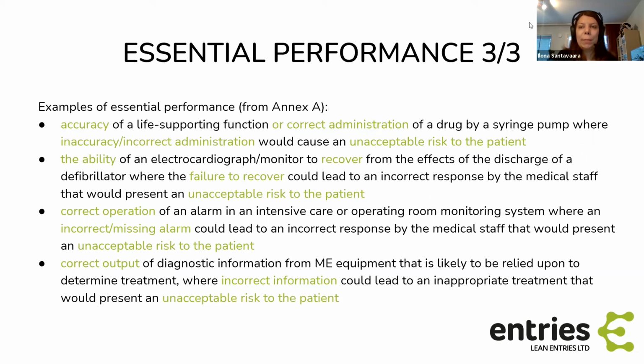And these are from the Annex A of the standard. So these are examples of essential performance. So it could be accuracy of a life-supporting function or correct administration of a drug by a syringe pump, where inaccuracy or incorrect administration would cause an unacceptable risk to the patient. Second example is ability of an electrocardiograph or monitor to recover from the effects of the discharge of a defibrillator. And here as well, failure to recover could lead to an incorrect response by the medical staff that would present an unacceptable risk to the patient. So the formula here is that there is always something that would present an unacceptable risk to the patient.